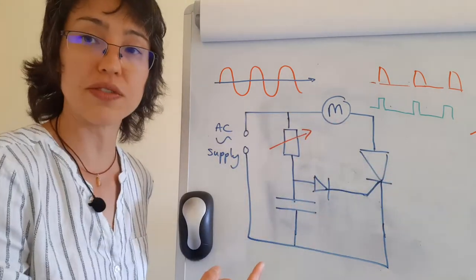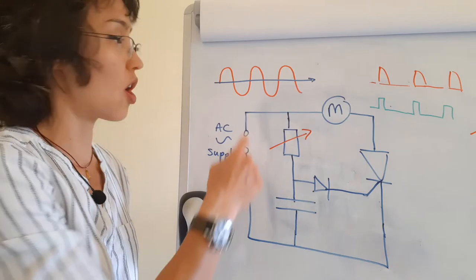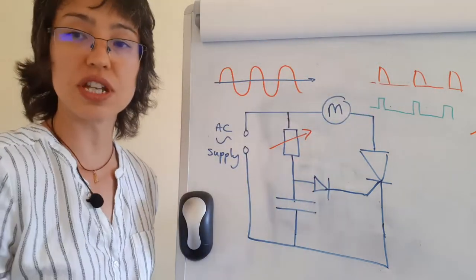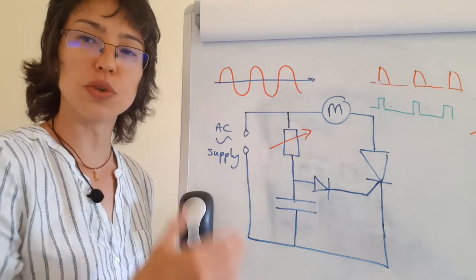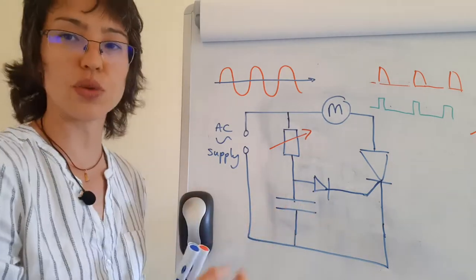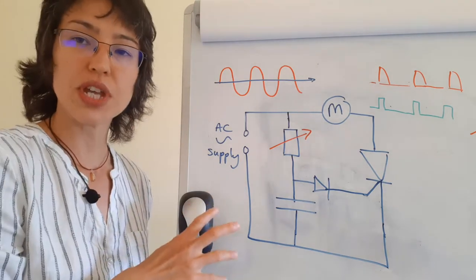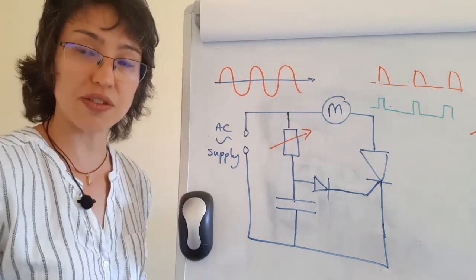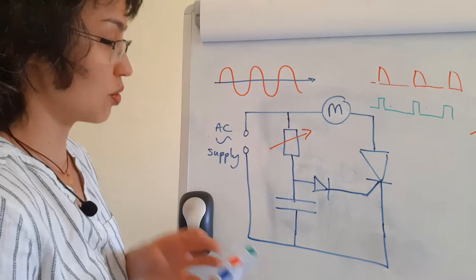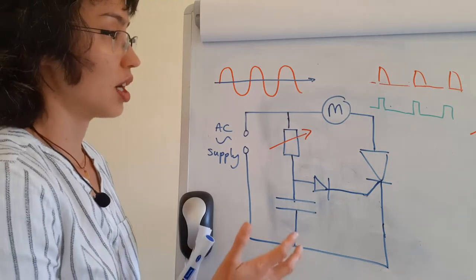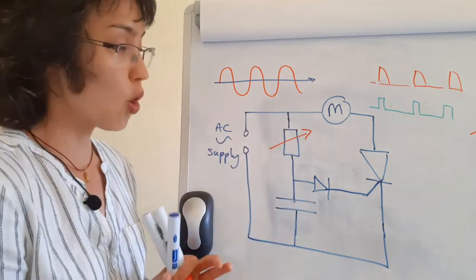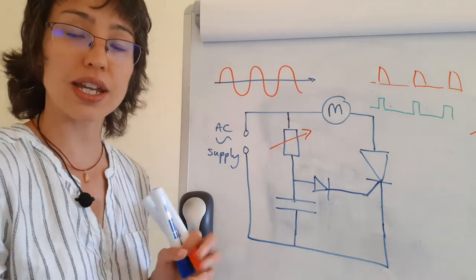Because a thyristor is a one-way device, you can only ever get a maximum of a half wave through this. So the maximum power would always only be half of what you would have if you had a full AC supply. So in order to get 100% phase control, we can build a rectifier circuit into this, or we can use something called a triac.